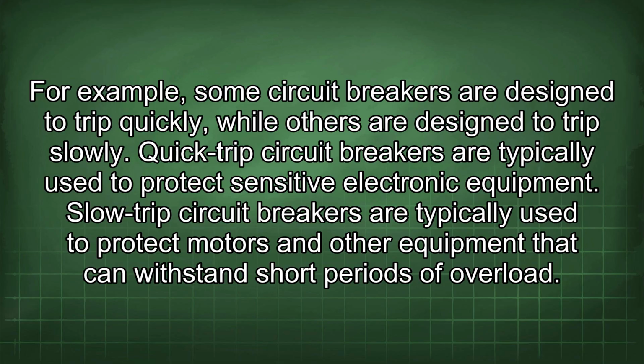For example, some circuit breakers are designed to trip quickly, while others are designed to trip slowly. Quick trip circuit breakers are typically used to protect sensitive electronic equipment. Slow trip circuit breakers are typically used to protect motors and other equipment that can withstand short periods of overload.